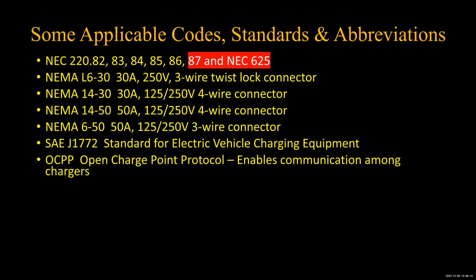And like they'll say, if you're going to have multiple chargers on a single circuit, there's going to be a current transformer at the origin of that circuit. And as soon as it reaches maximum current, that charge controller is going to send messages out to the chargers and say, okay, guys, you got to work it out here now so that this is how many amps you've got. And either I'm going to decide for you or you're going to decide not to overload this circuit. And it's generally a combination of the two deciding. And sometimes even the car could get involved because the car would probably be programmed to say, if the electricity is too expensive, don't buy it until the price comes down. If in fact you're plugged into a variable price source of electricity, which probably some are going to be like that, I'm sure.